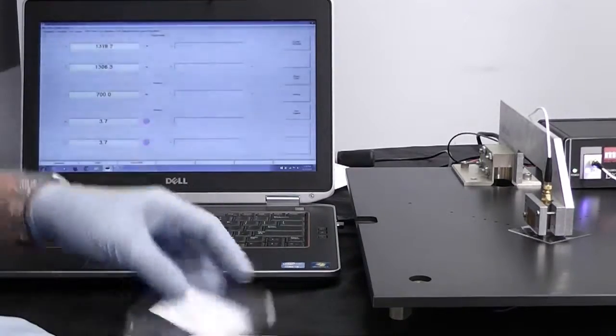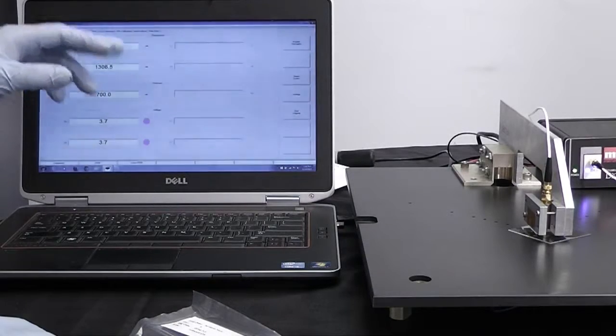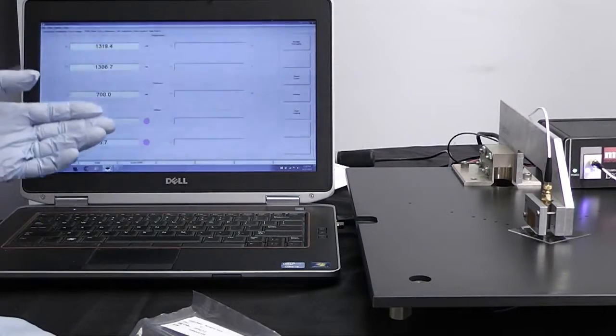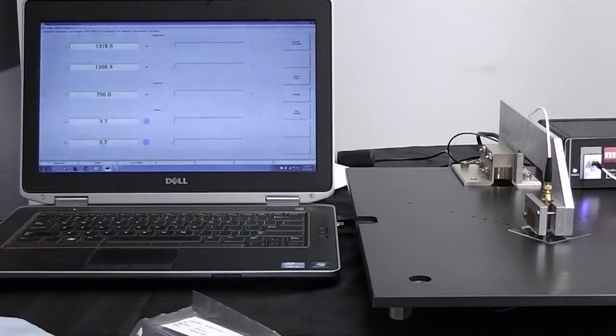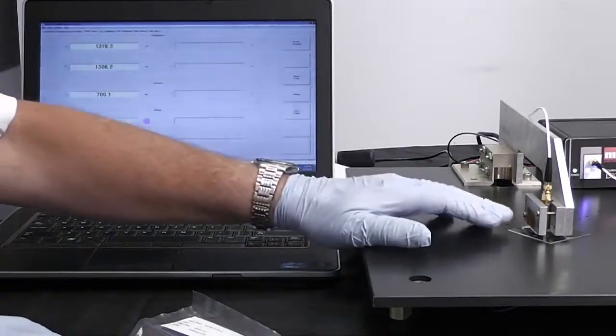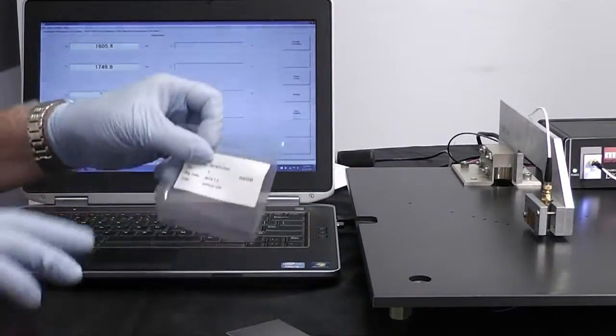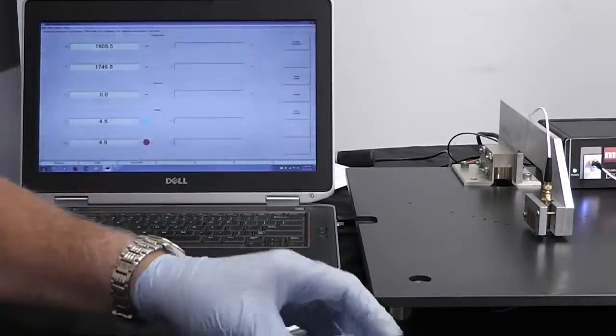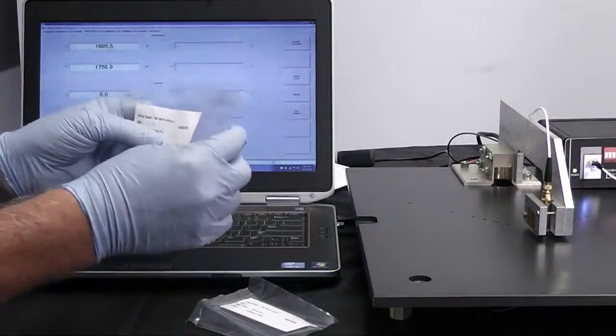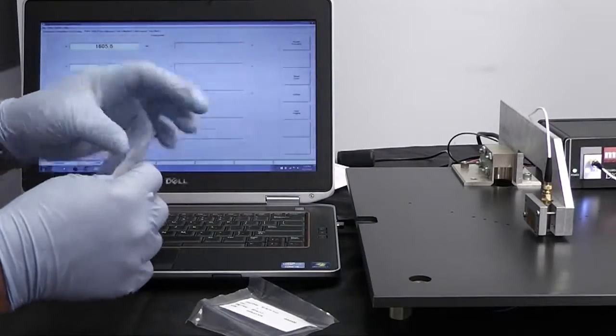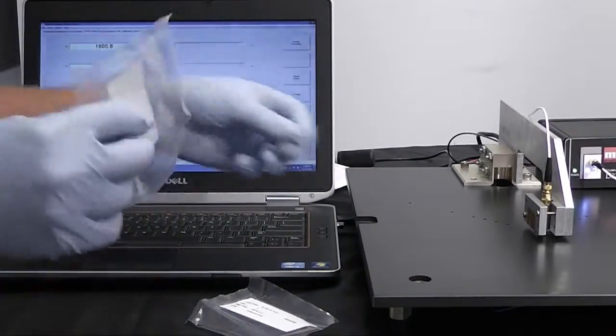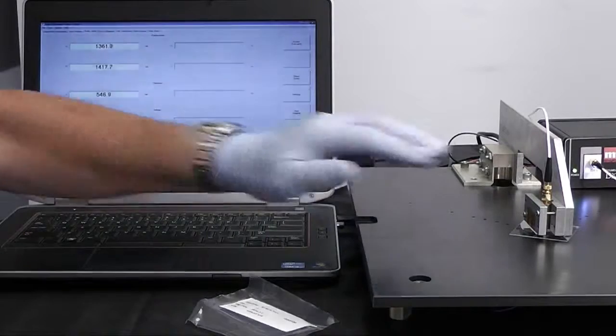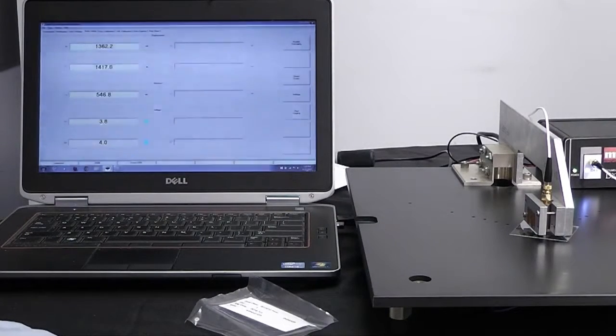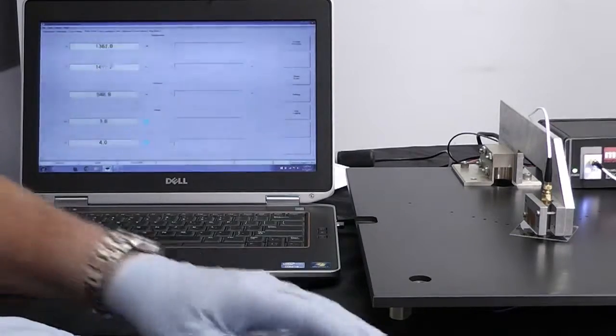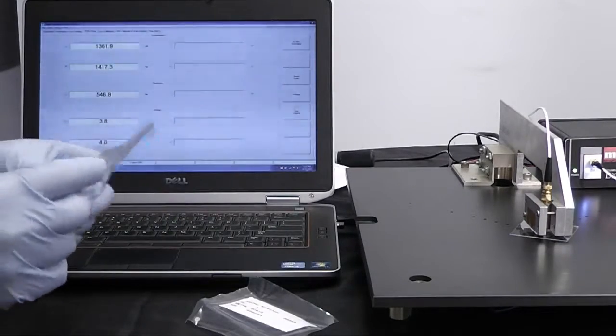You just take one known thickness and you go to the thickness calibration tab, as we've seen before, and enter that. So I'm reading 700 microns for this sample. The manufacturer says it's 700 microns. We're going to look at next a 550 micron sample. And we're reading within 3 microns of that sample, which is well within the accuracy of what they're stating on their envelope here.